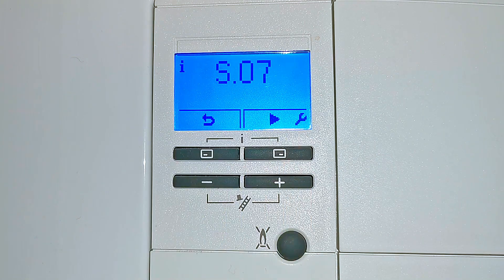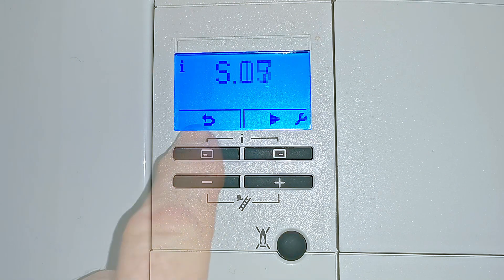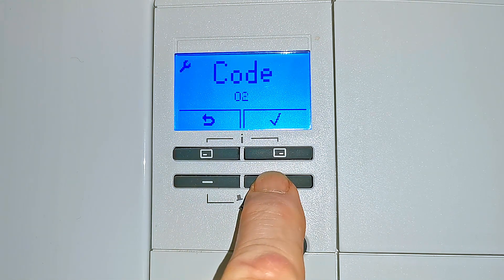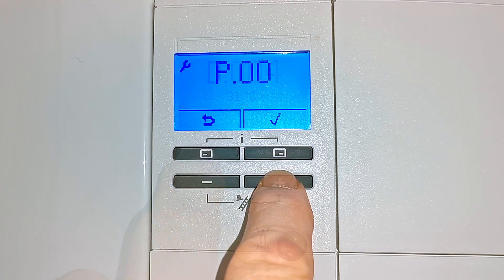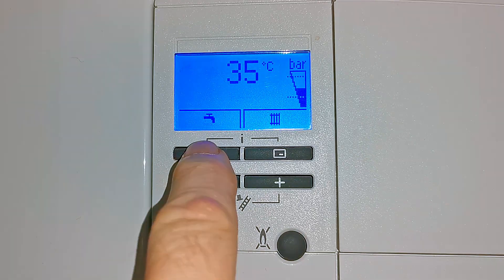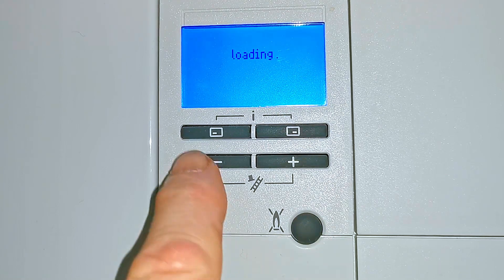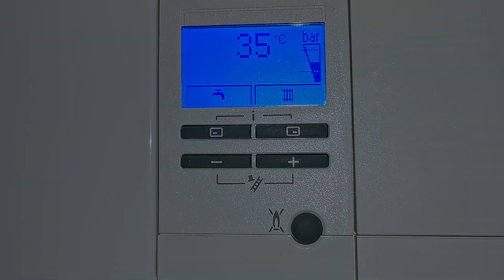This boiler has the standard information mode — the S mode — where we can check exactly what the boiler is doing at this point in time, though this is more useful for engineers. We can also go into the engineering mode where we have the standard Vaillant engineering settings: the D settings where we can adjust the boiler parameters, the P settings, and then we have the fault history. The final button on the front of the boiler is a reset button. If you ever get a fault code come up in the display, you push this button to reset the boiler, and now the boiler is reset.